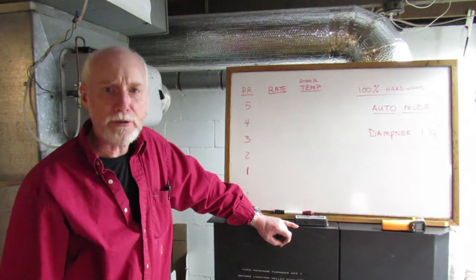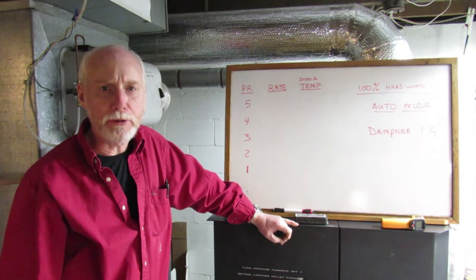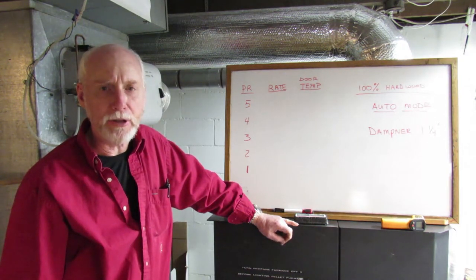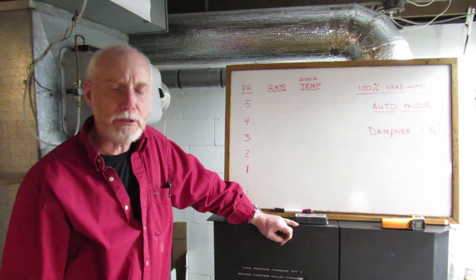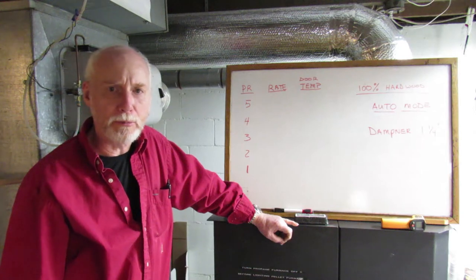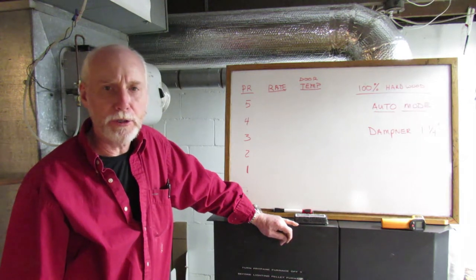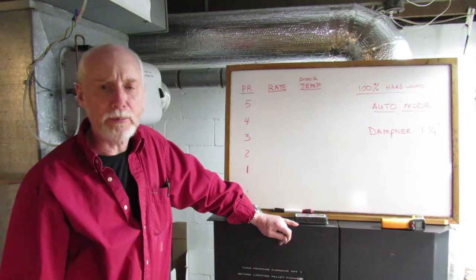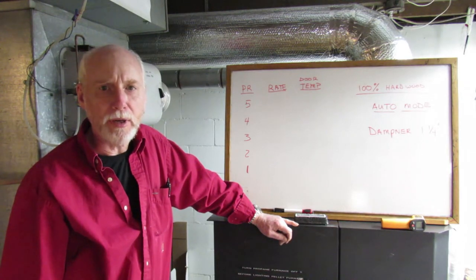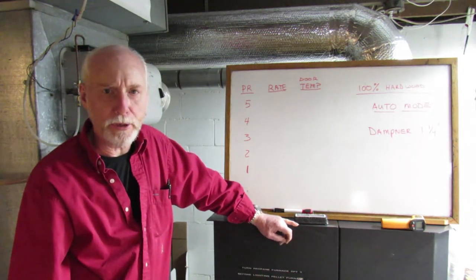I found over last year and this year that the stove runs much smoother if you eliminate, in other words don't use, setting number 5 for your high temp. And the reason for this is that your stops are set according to your computer board from your PR1 setting and your PR5 setting. So when you're running a high temp on PR5, what's happening is you're bumping up against the top stops, the limits on that computer board in there.